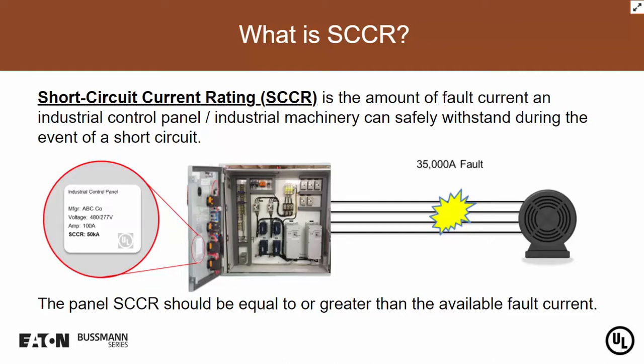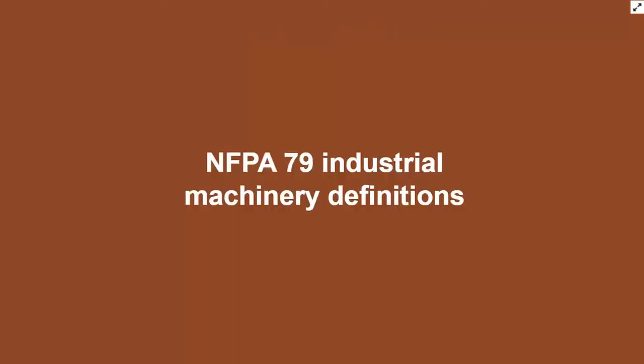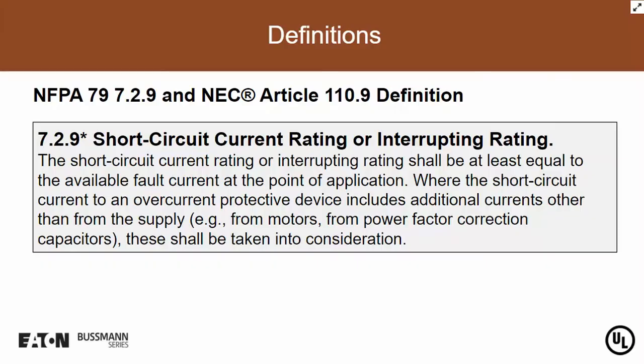So let's continue on with some important definitions that I believe will help you further understand the concept of short circuit current rating and available fault current. Here we have an excerpt from NFPA 79, specifically paragraph 7.2.9, and this is also found in the National Electrical Code in Article 110, specifically section 110.9. A short circuit current rating or interrupting rating shall be at least equal to the available fault current at the point of application.